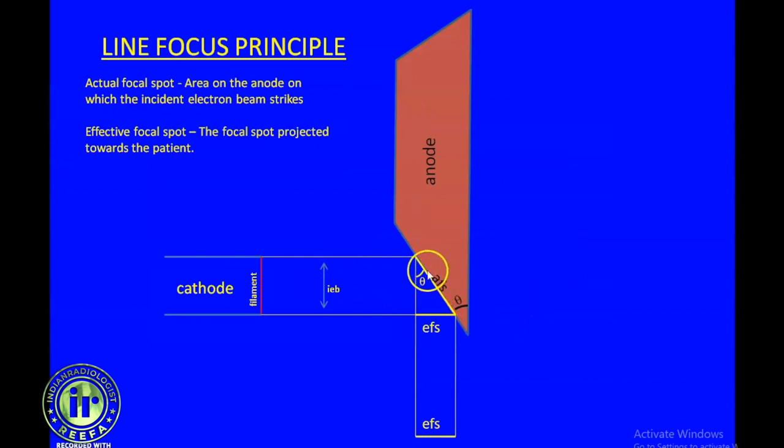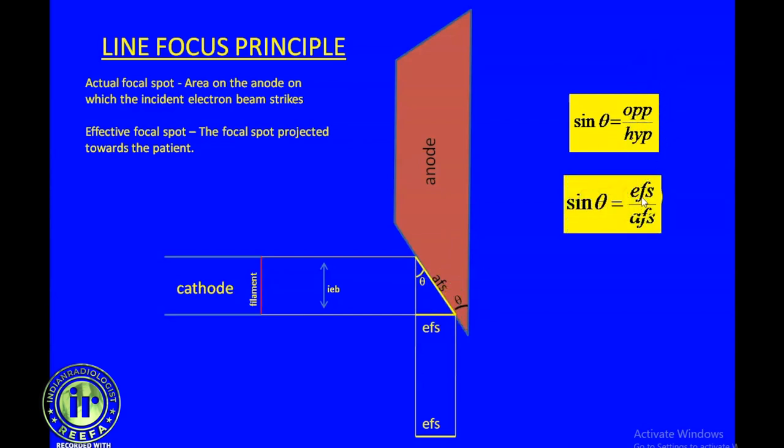When the beam strikes the anode and this is the projected beam called the effective focal spot, you can see these two beams are making a right angle triangle. This is the anode angle constituting one angle of this right angle triangle. In basic high school trigonometry, sin θ equals opposite by hypotenuse. The opposite side is the effective focal spot. The hypotenuse is the actual focal spot. So sin θ = efs/afs, and from this we get efs = sin θ × afs. If we know the anode angle and the width of the actual focal spot, we can calculate the size of the effective focal spot.